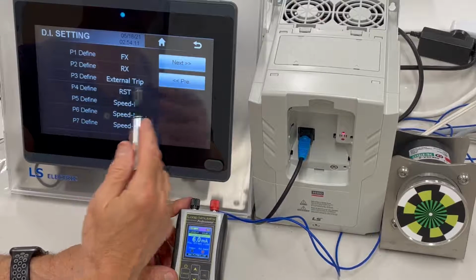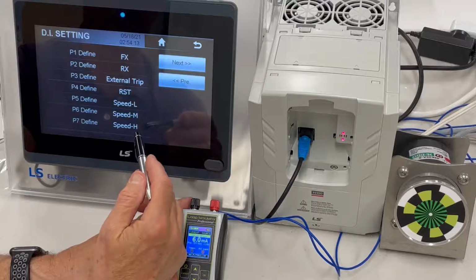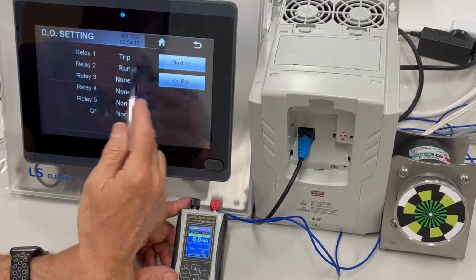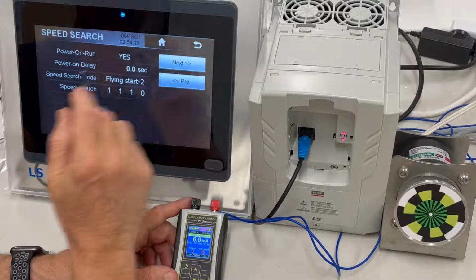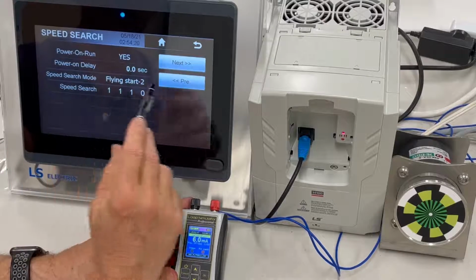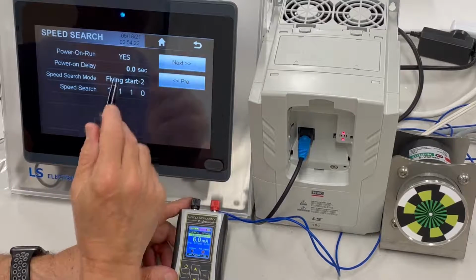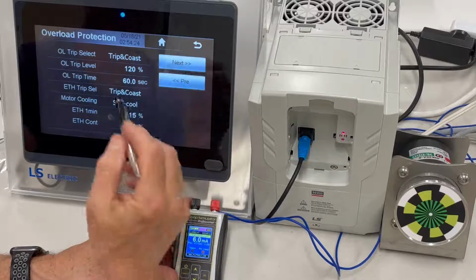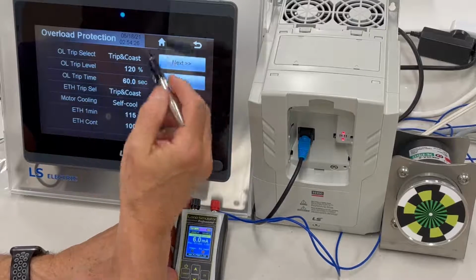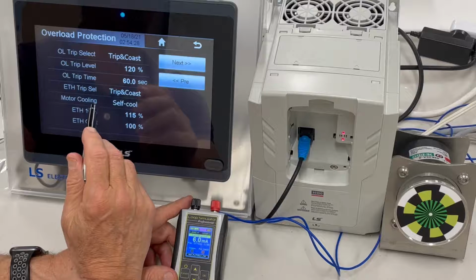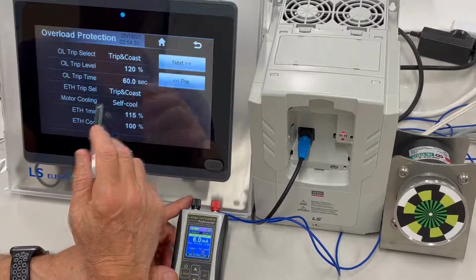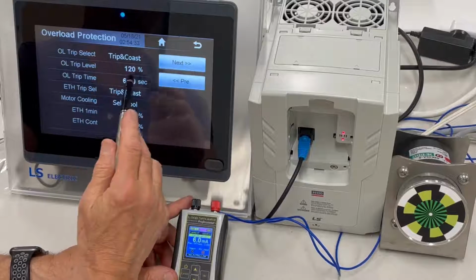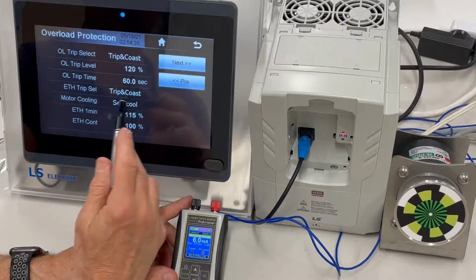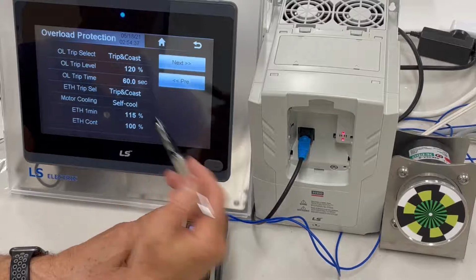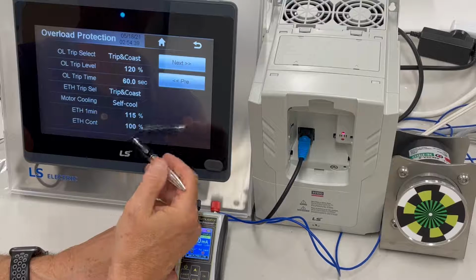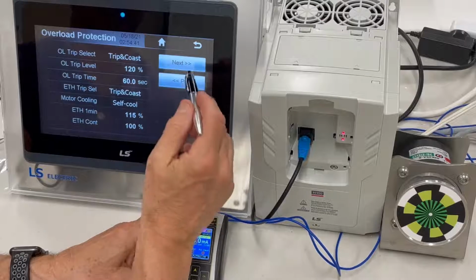We have forward, reverse, external trip, reset, speed low, medium, and high. And then have relays for trip and run. And then power on, yes. Flying start also, there's different types. I won't get into the details explaining them, but depending on your application, you can select those to give you the right type of flying start. Trip and coast, overload protection, time, the motor is self-cooling, and then different other parameters you can set.